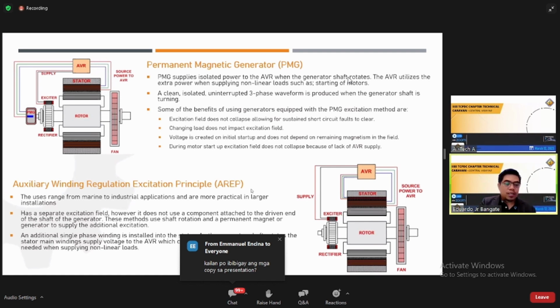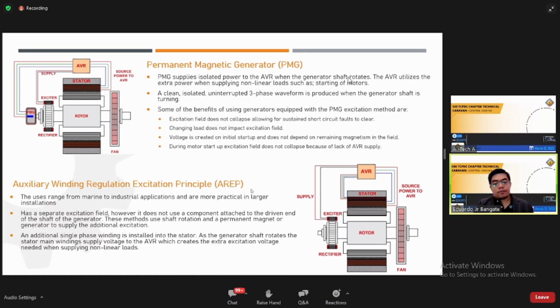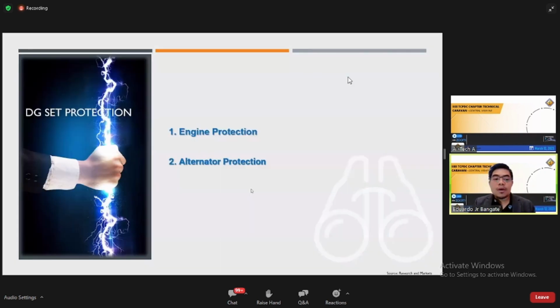So it says that an additional single phase winding is installed into the stator. As the generator shaft rotates, the stator main winding supplies voltage to the AVR, which creates the extra excitation voltage needed when supplying non-linear loads. All right, so that's the basics of our control. Now let's go to DG Set protection.